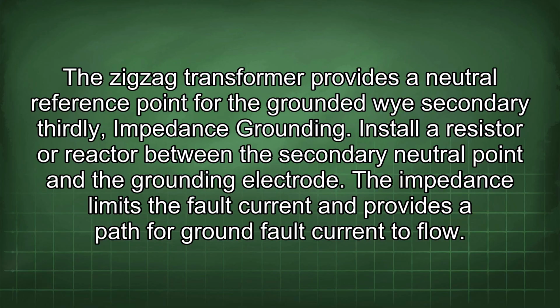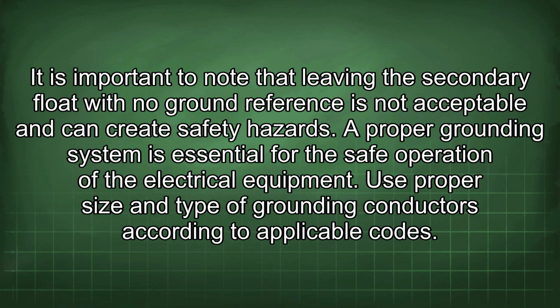Thirdly, impedance grounding. Install a resistor or reactor between the secondary neutral point and the grounding electrode. The impedance limits the fault current and provides a path for ground fault current to flow. It is important to note that leaving the secondary floating with no ground reference is not acceptable and can create safety hazards. A proper grounding system is essential for the safe operation of the electrical equipment.